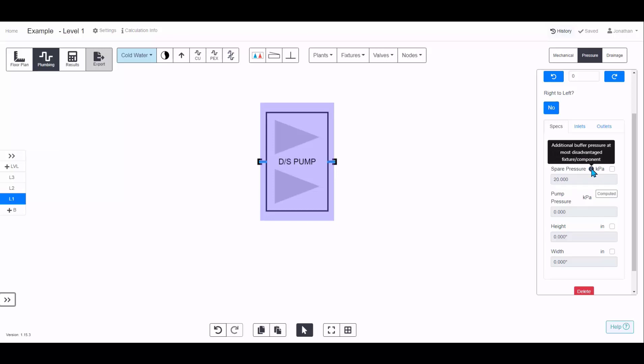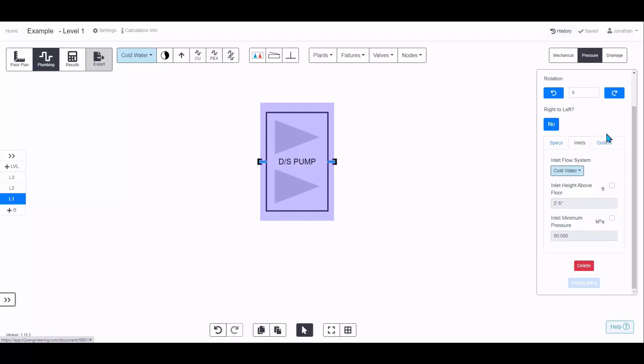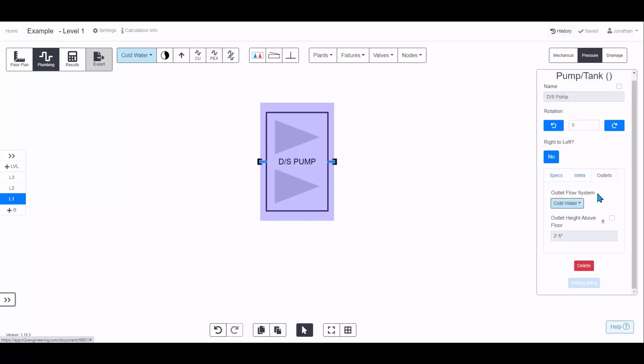You can add a spare pressure which defaults to 20 kPa — this accounts for bends or fittings not modelled in h2x. You can add additional pressure or set it to zero here. You can also set the inlet flow system and connection height, and you'll get a warning if you don't meet the minimum inlet pressure. Set it to zero or negative to suppress that warning. The outlet is similar: choose the flow system and the height.